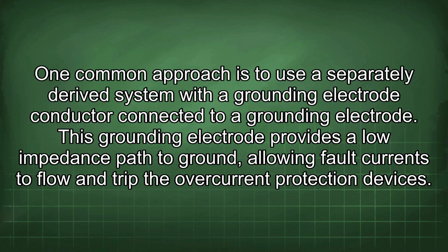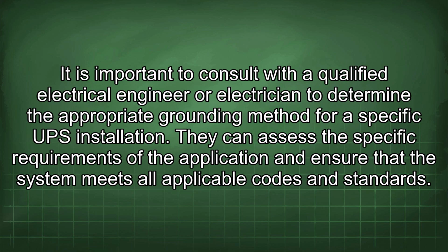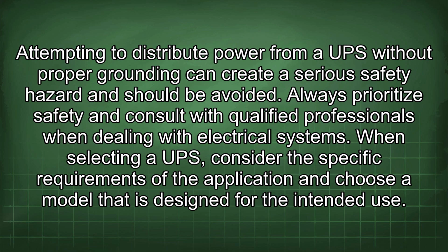This grounding electrode provides a low impedance path to ground, allowing fault currents to flow and trip the overcurrent protection devices. It is important to consult with a qualified electrical engineer or electrician to determine the appropriate grounding method for a specific UPS installation. They can assess the specific requirements of the application and ensure that the system meets all applicable codes and standards. Attempting to distribute power from a UPS without proper grounding can create a serious safety hazard and should be avoided. Always prioritize safety and consult with qualified professionals when dealing with electrical systems.